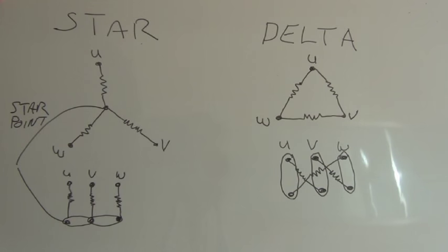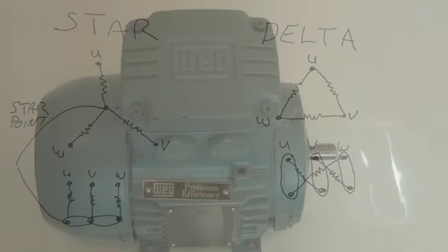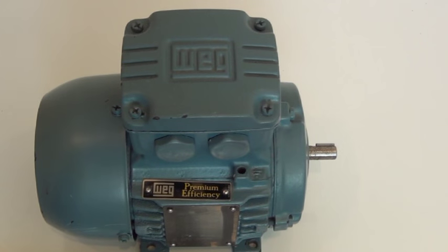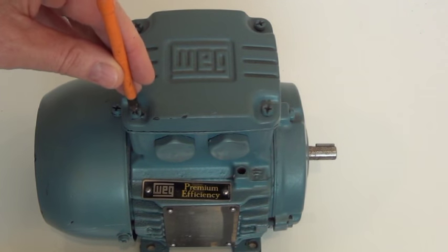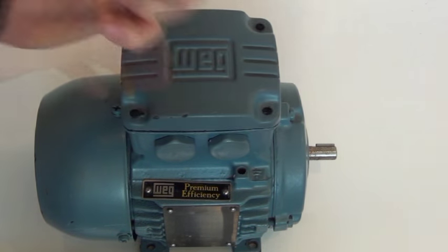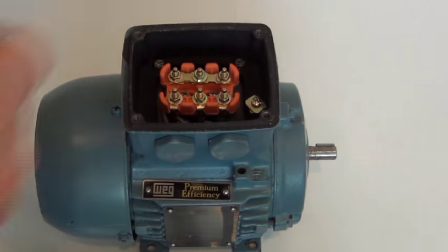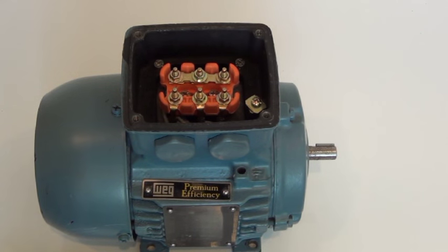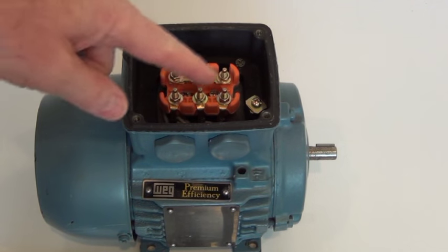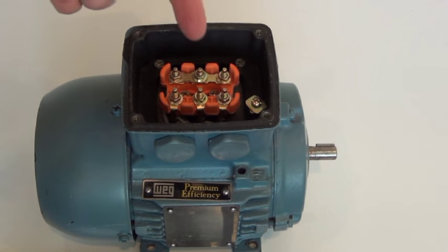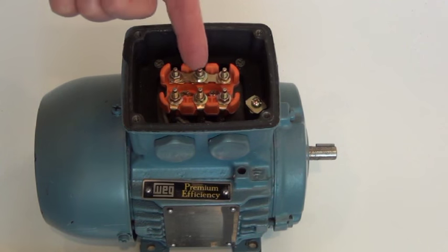So let's have a look at a motor terminal block. Here I have a WEG premium efficiency IE3 motor. I'm going to remove the terminal box cover and remove the gasket. This exposes the terminals, and as you can see from our previous discussions, we have a star point here, so this particular motor is connected in the star configuration.